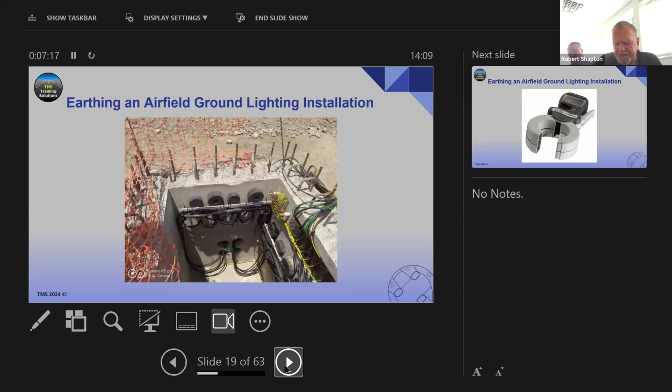And an AGL earthing system is required for every primary route, not every primary circuit. And by this, you mean it may be that you have 5 different circuits running in the same trench. You do not need an individual earthing circuit for each one of those circuits. Then that trench, one earthing circuit would be adequate as long as it connects with all the relevant points.